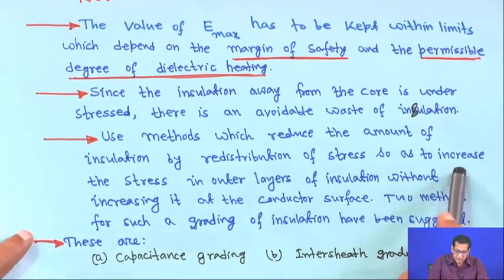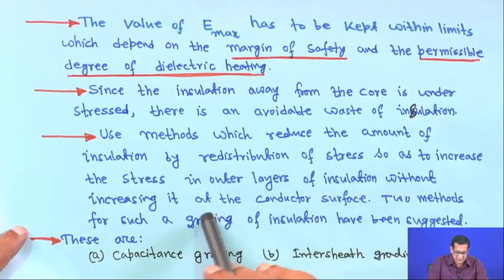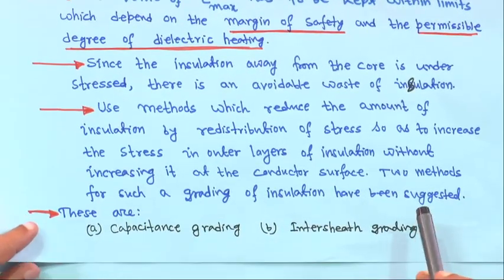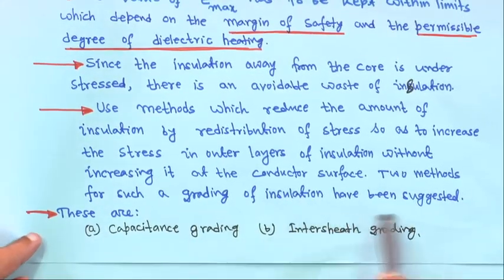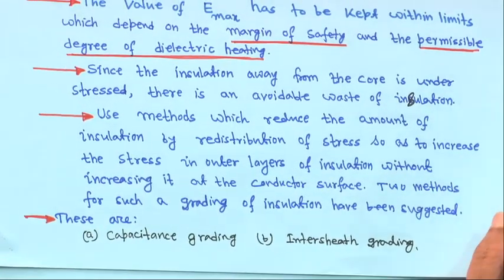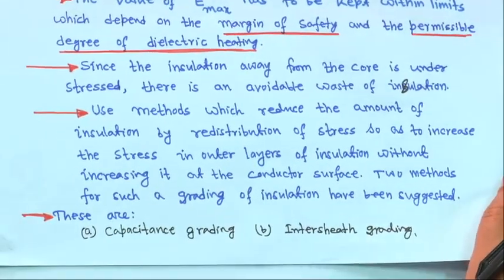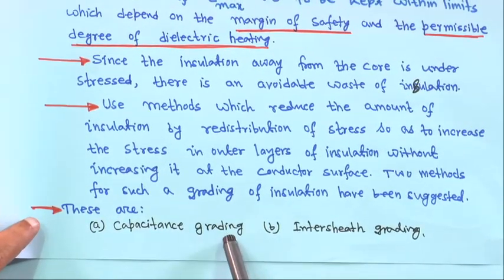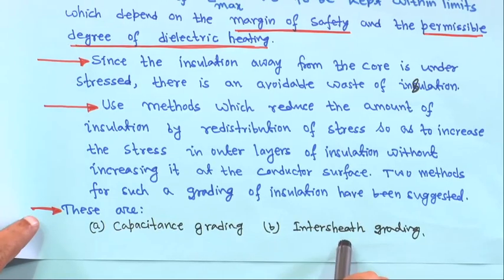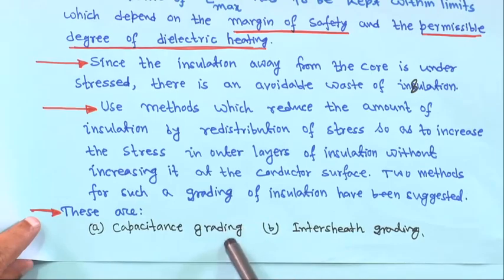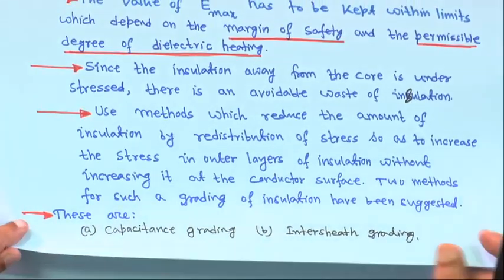By redistribution of stress, we increase the stress in outer layers of insulation without increasing it at the conductor surface. Two methods are generally recommended: capacitance grading and intersheath grading. In reality, implementation of both is difficult, so they are rarely used, but we will see how things can be done.